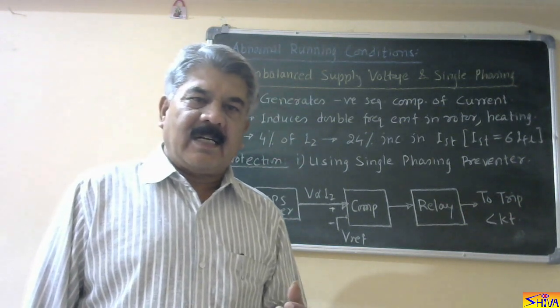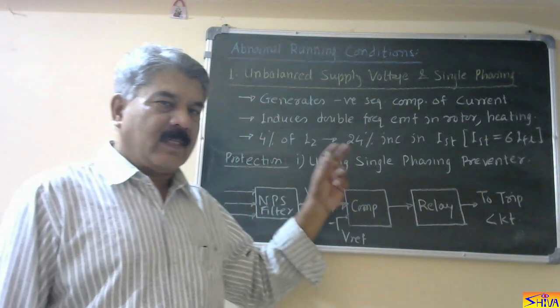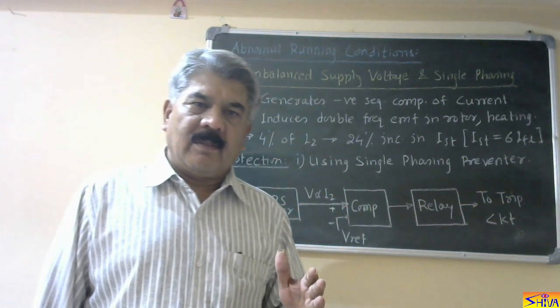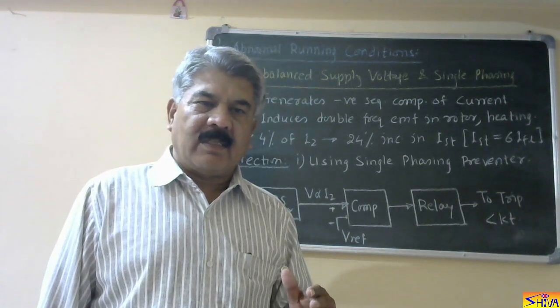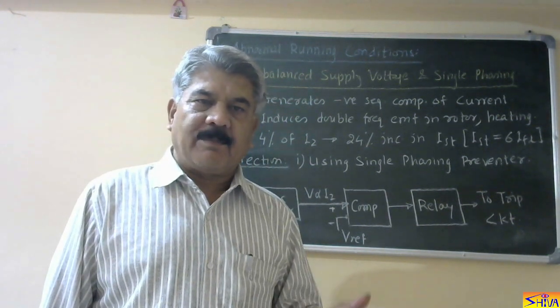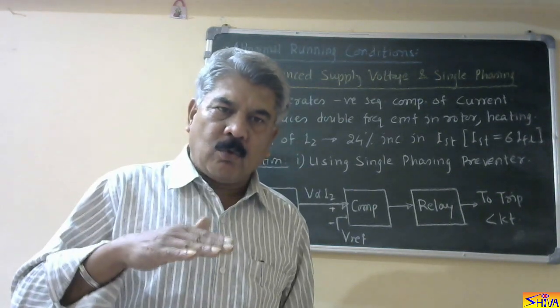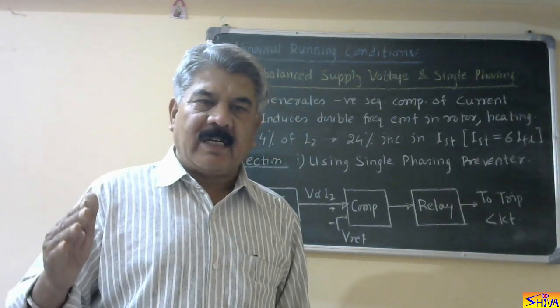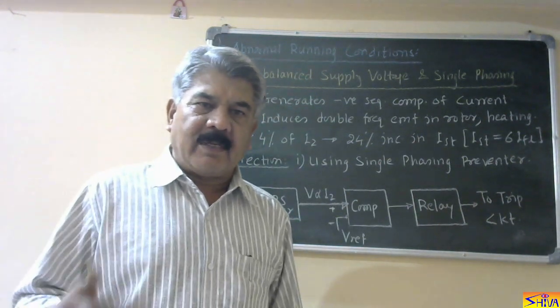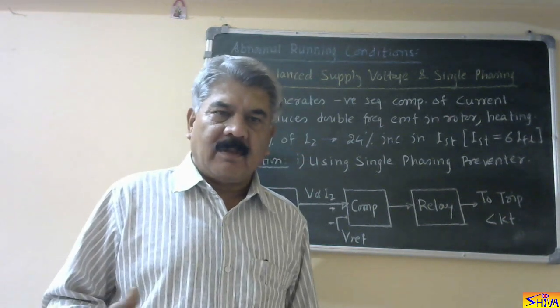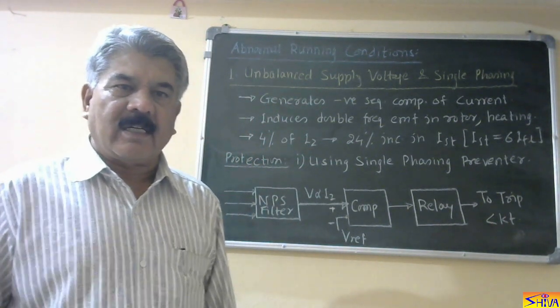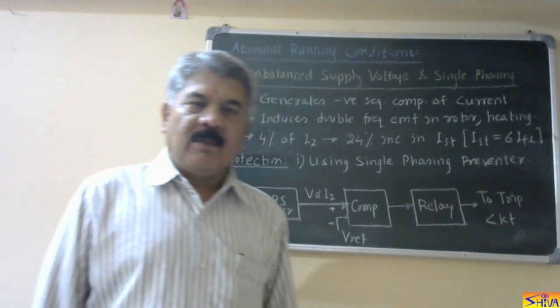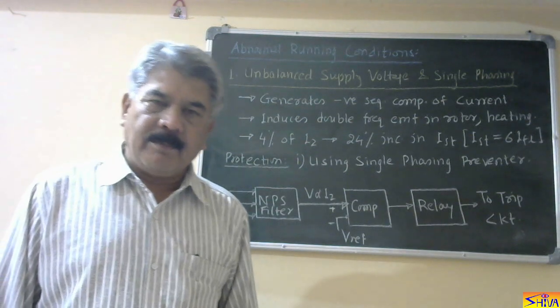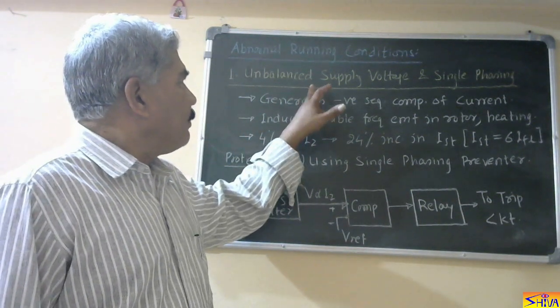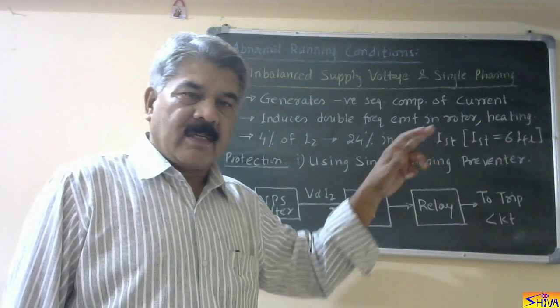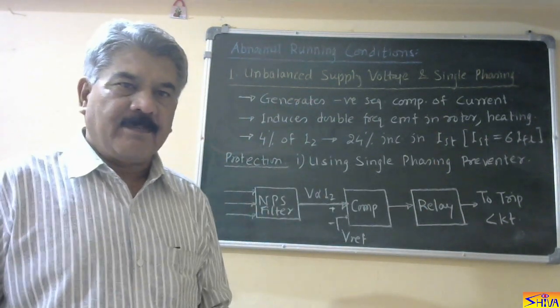Now if it is a delta connected motor, then even when only two phases are there and the motor is lightly loaded, there is no worry, because that is not going to increase the temperature considerably. But when the load goes beyond 70% of the rated value for a delta connected induction motor and single phasing is there, then temperature starts increasing severely and fast, and current starts increasing fast. So that is detected by the overload protective device. Therefore, for small as well as medium sized induction motors, separate protection for unbalanced supply voltage and single phasing is not required. Next protection is under voltage.